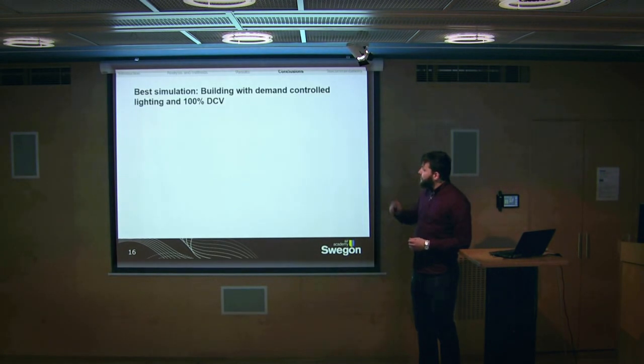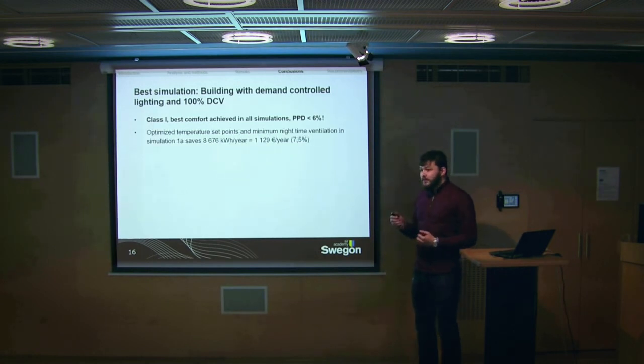So in conclusion, the best simulation is the building with demand-controlled ventilation and demand-controlled lighting. The best indoor climate is achieved with a PPD of lower than 6%. Optimizing the temperature set points and minimizing the nighttime ventilation, which is the first step in optimizing the indoor climate, saves almost 9,000 kilowatt hours per year, equal to about 1,100 euros per year in operating cost—a 7.5% savings in operating costs each year, just by optimizing the temperature set points and guaranteeing the best indoor climate for the lowest energy consumption.